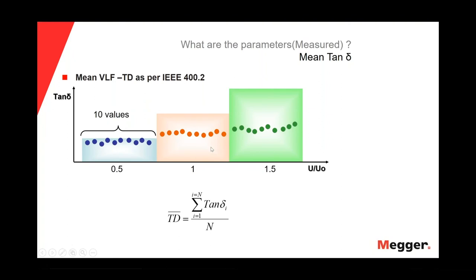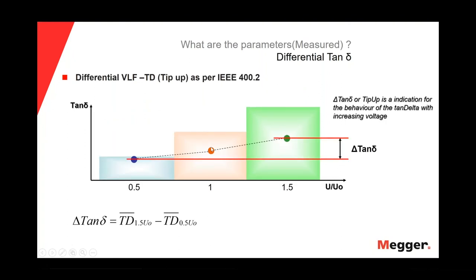The second parameter we will measure is the differential VLF tan delta, or tip-up, also called the delta of the tan delta. The delta of the tan delta is the mean value of the tan delta at 1.5 U0, from which we subtract the mean value of the tan delta we get at 0.5 U0, as we can see in this equation. This is the second parameter we will measure.